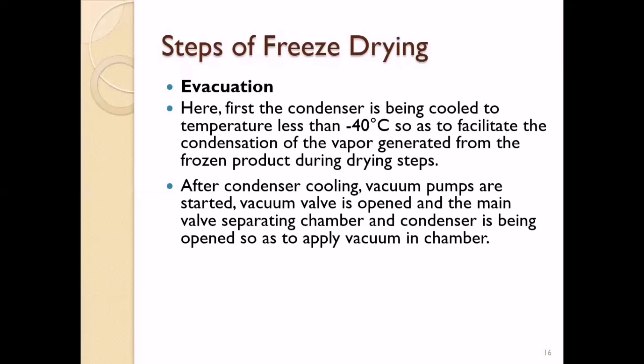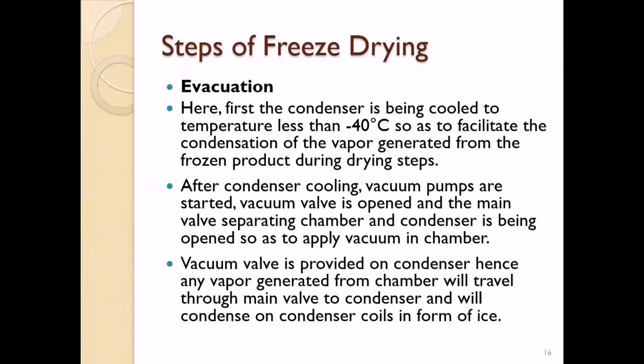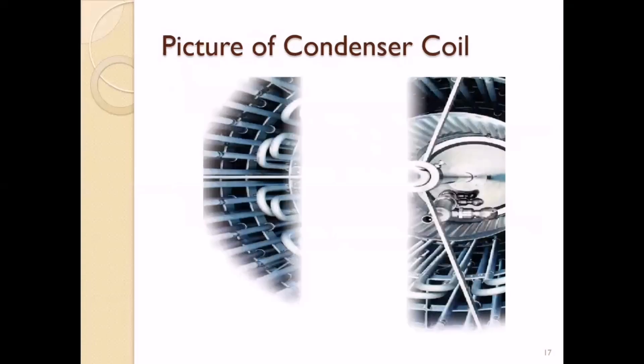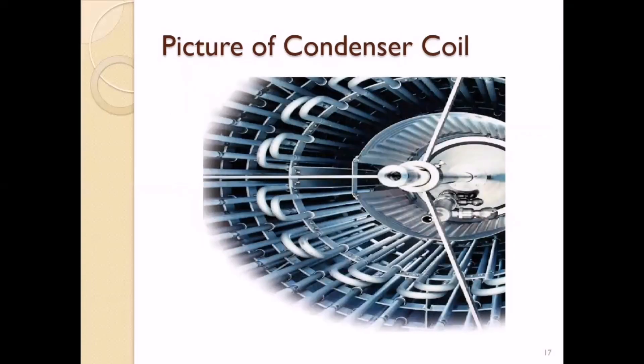Any vapor generated from the chamber travels through the main valve to the condenser and condenses onto the condenser coils in the form of ice. The condenser coil is a pipe structure through which refrigerant gas is passed to achieve temperatures below minus 40 degrees, allowing water vapor to directly condense onto the coils.